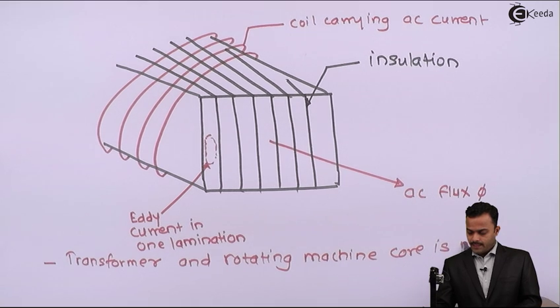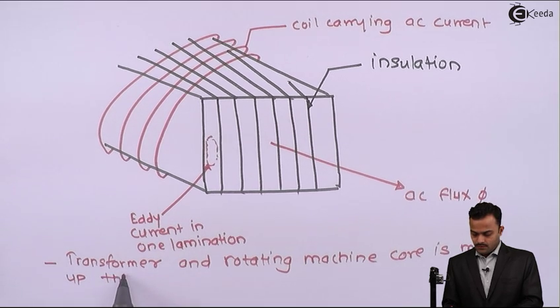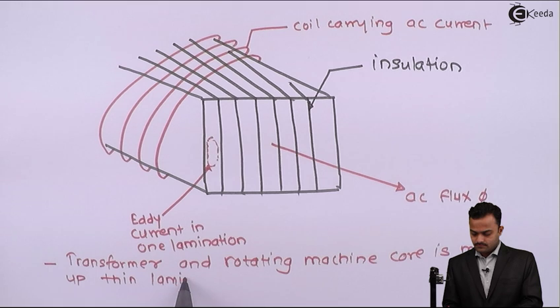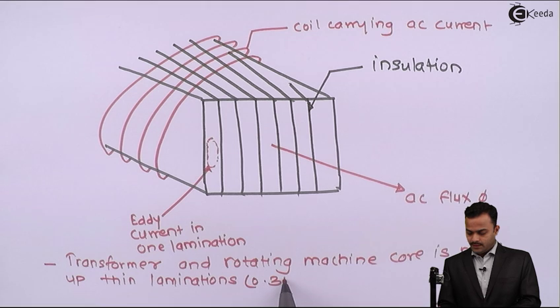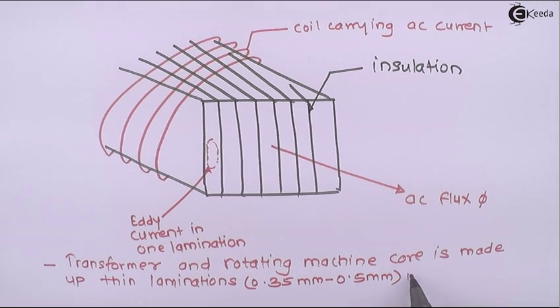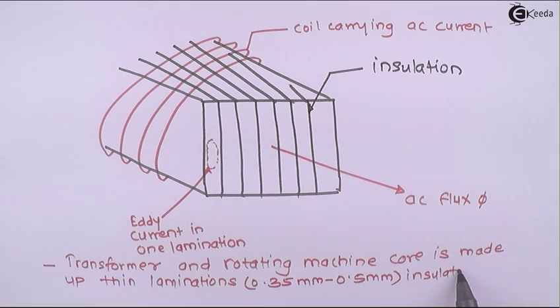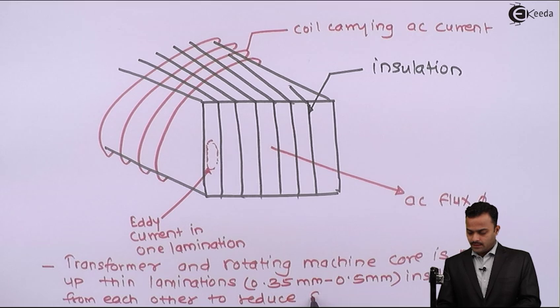...are made up of thin laminations. And the width of this lamination sometimes will be 0.35 mm to 0.5 mm, but these laminations are insulated from each other to reduce eddy current losses.